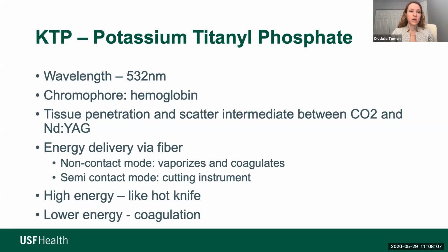So there's two options for that. There's the non-contact mode, which vaporizes and coagulates. And then there's the semi-contact mode, where it acts more like a cutting instrument. At high energies, it acts like a hot knife, whereas at lower energies, it will function more to coagulate.